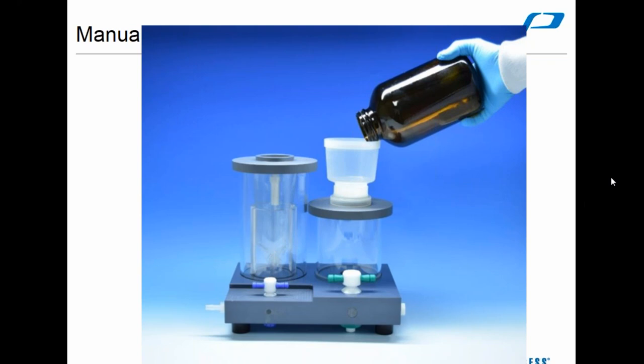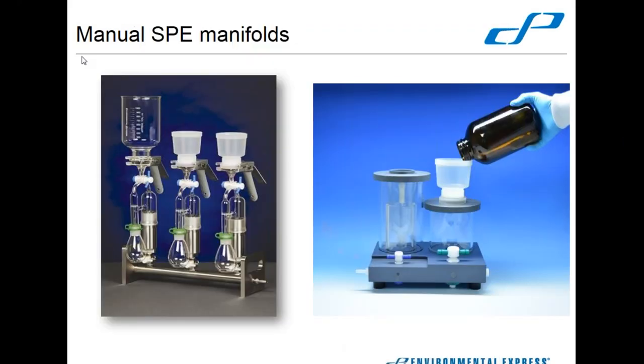The goal here was to make it a lot simpler as far as possibility of breaking and eliminating potential leaks in the system. There are no stopcocks to have to turn one way or the other. There's no worries about glass junctions and vacuum pulling too strongly. We had experienced some issues with some stopcocks not being the best seal and having some leak around those. Going to this particular setup has removed all those particular problems.